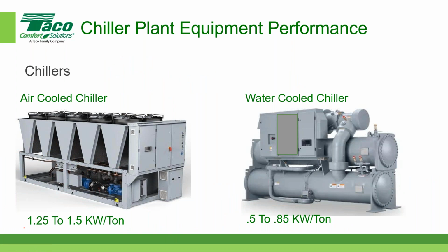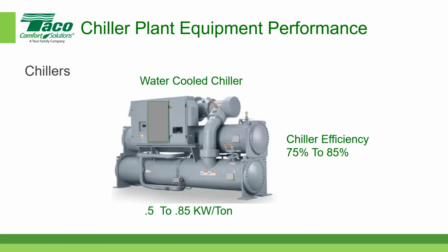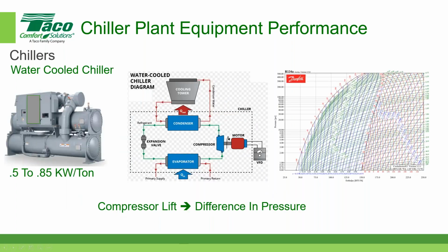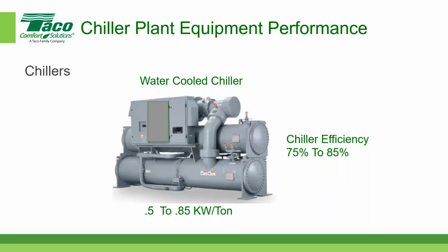Okay, all right, we're clear. So let's go on and talk a little bit about a water-cooled chiller. You can certainly find water-cooled chillers that are less than 0.5 kW per ton. You can certainly find them slightly more than 0.85 kW per ton. But I kind of like this mid-range right here.